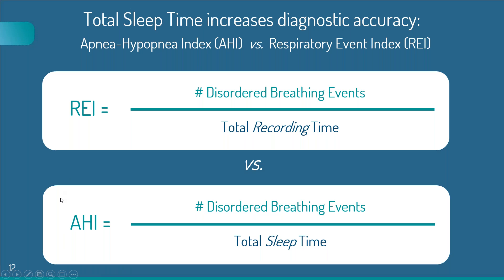WatchPat stands in contradistinction to most other home testing units, which may count up the sleep disorder breathing events but divide those events by total recording time rather than total sleep time. Because recording time is always greater than total sleep time, the ability of these devices to detect and classify patients with mild, moderate, and severe sleep apnea is somewhat reduced or less sensitive than the WatchPat device.